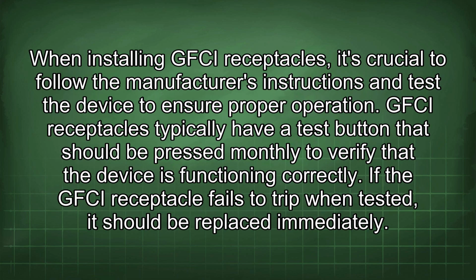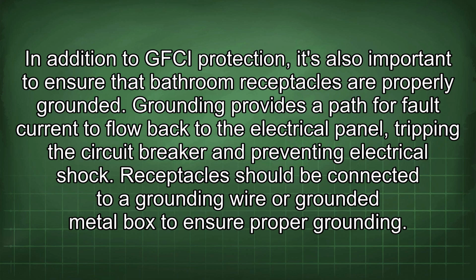When installing GFCI receptacles, it's crucial to follow the manufacturer's instructions and test the device to ensure proper operation. GFCI receptacles typically have a test button that should be pressed monthly to verify that the device is functioning correctly. If the GFCI receptacle fails to trip when tested, it should be replaced immediately. In addition to GFCI protection, it's also important to ensure that bathroom receptacles are properly grounded. Grounding provides a path for fault current to flow back to the electrical panel, tripping the circuit breaker and preventing electrical shock. Receptacles should be connected to a grounding wire or grounded metal box to ensure proper grounding.